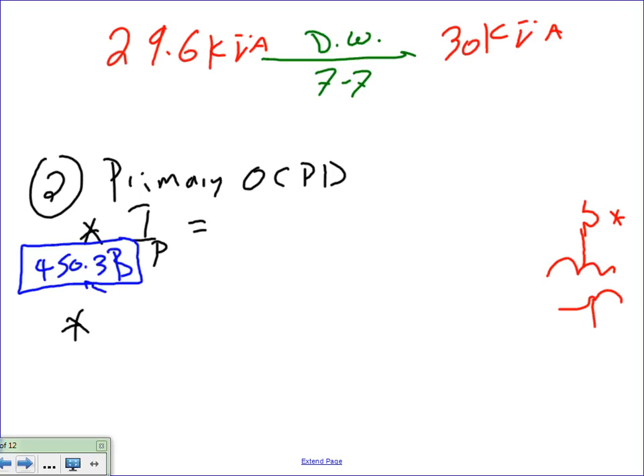Now, Chris, say you decided to add another 25% for future expansion. First, you add that on to the 29.6, then you size your transformer. That's where you have to make up your mind. I made up my mind, that's all I need on this transformer, and I'm done. So that will be a 30 kVA transformer.